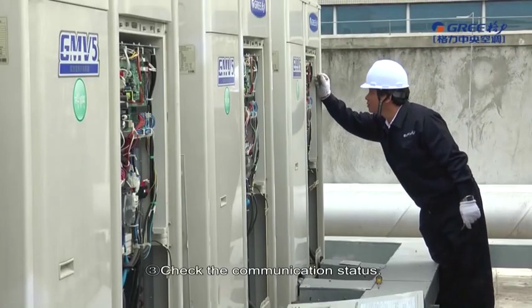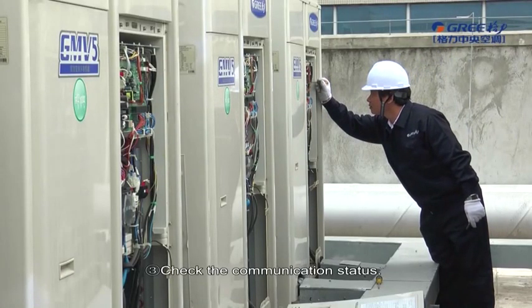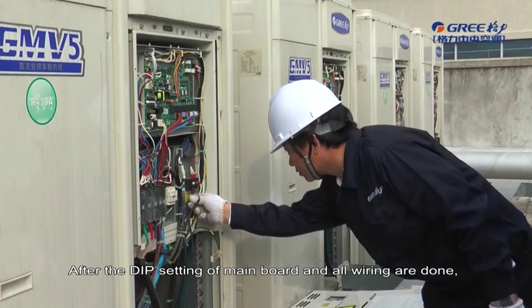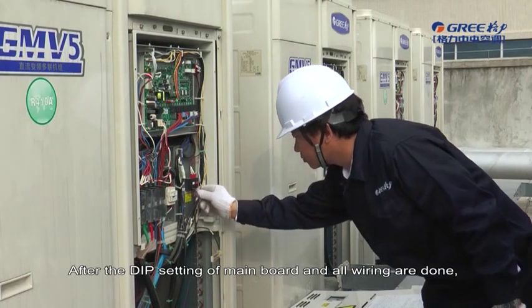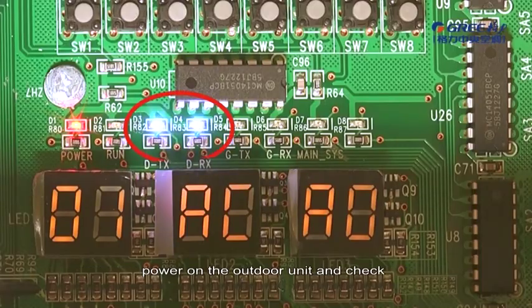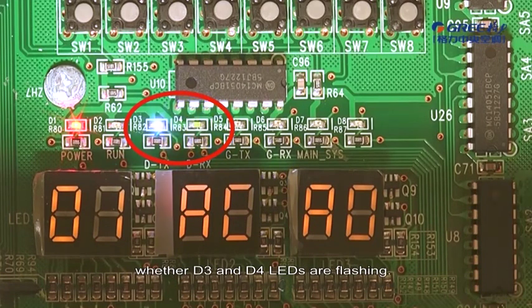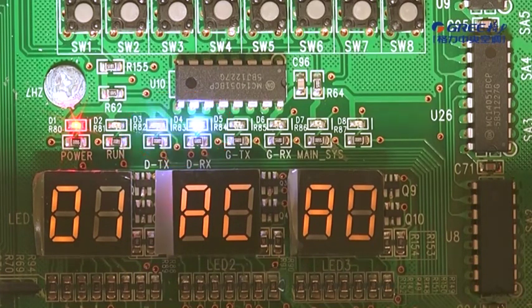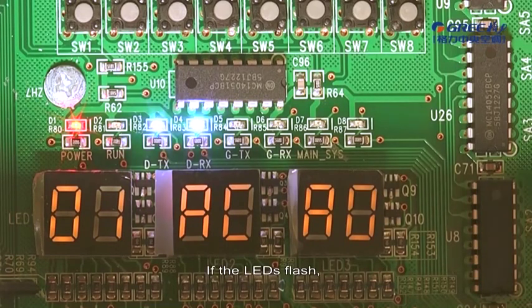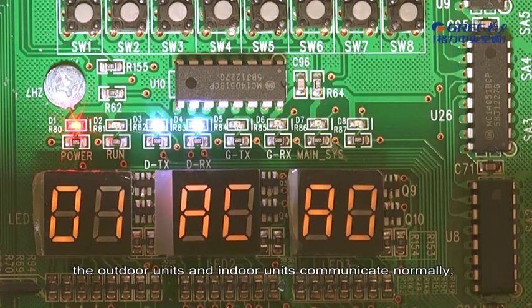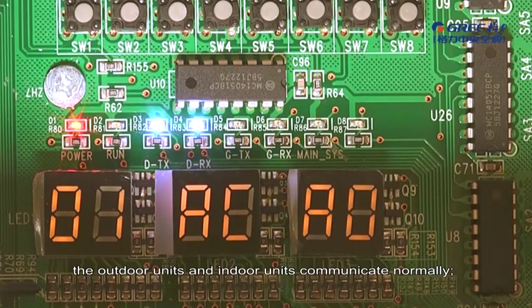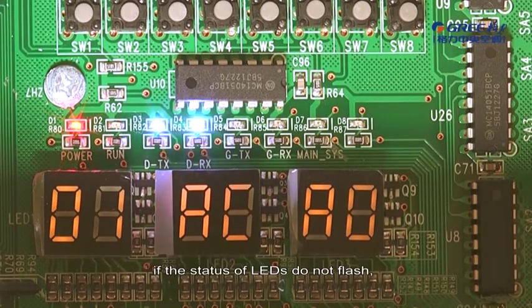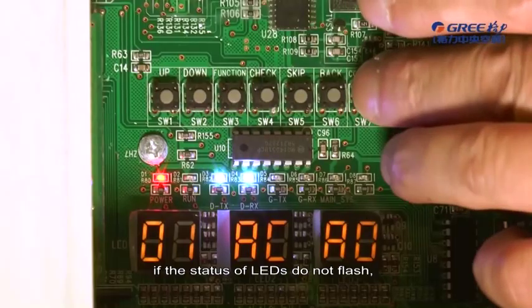3. Check the Communication Status. After the DIP setting of main board and all wiring are done, power on the Outdoor Unit and check whether D3 and D4 LEDs are flashing. If the LEDs flash, the Outdoor Units and Indoor Units communicate normally. If the LEDs do not flash, communication is faulty.